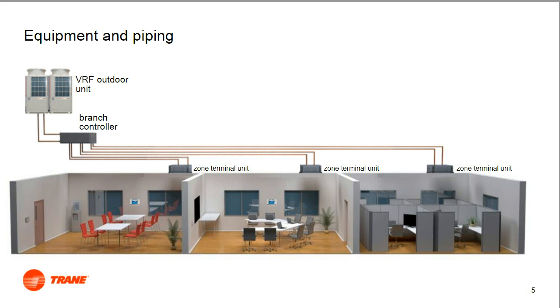VRF systems are known for using variable speed compressors and fans, but they have several unique characteristics beyond their variable speed nature. First, VRF systems have one outdoor unit connected to many indoor units. This gives VRF systems their zoning capability. Second, they are reversible heat pumps. This enables electrified high COP heating. And third, they can offer simultaneous heating and cooling capabilities. This means some zones can be in heating while others are cooled at the very same time. It does this by recovering heat within the system.